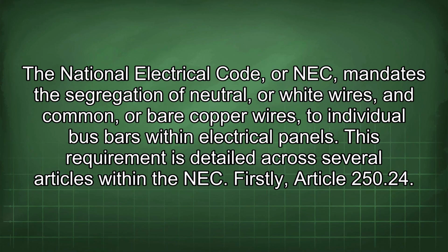The National Electrical Code, or NEC, mandates the segregation of neutral, or white wires, and common, or bare copper wires, to individual bus bars within electrical panels. This requirement is detailed across several articles within the NEC.